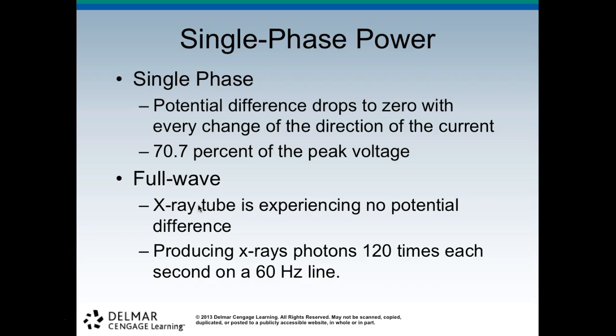So 70.7% of peak voltage, so we're losing a lot there. With full wave, the X-ray tube is experiencing no potential difference. So the X-ray photons are produced 120 times each second on a 60 hertz line.